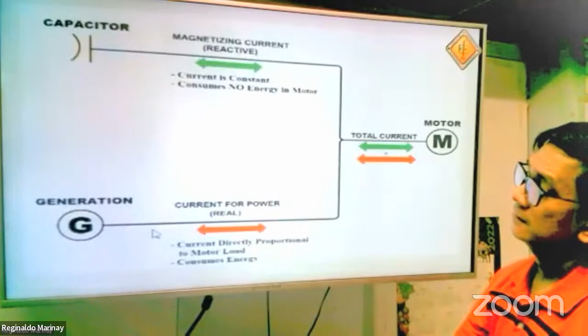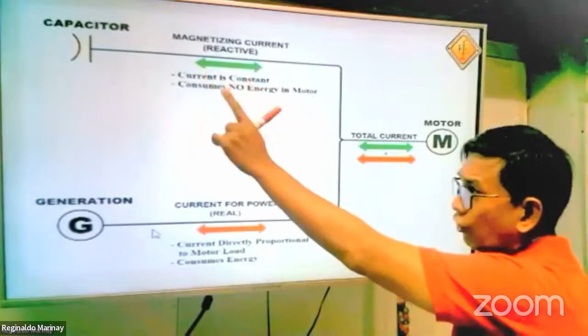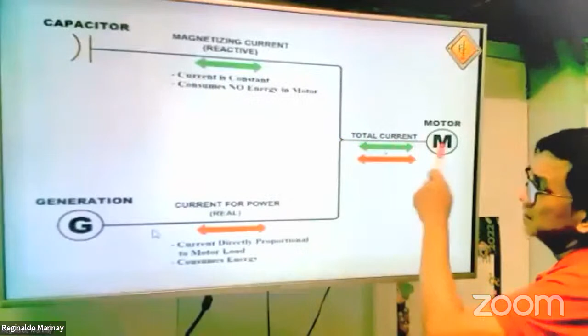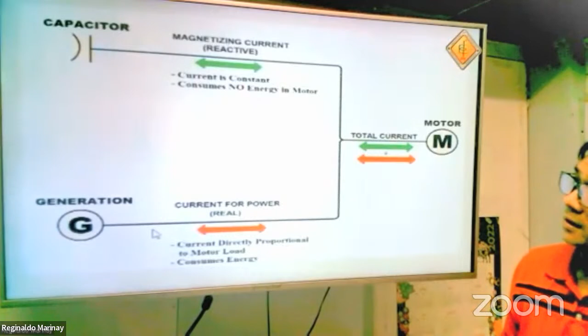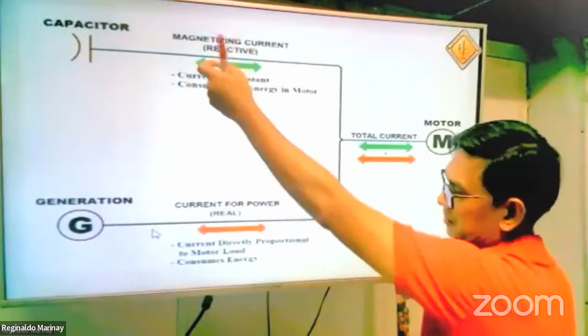Initially, it took these two types of current: the magnetizing current and the real current. But when you put a capacitor on the system, take a look—of course this is an ideal discussion for power factor correction, because you will see that the green color, the magnetizing or reactive current, is all being delivered by the capacitor. That is what I mean by ideal. But in reality, the source still delivers reactive current, but it decreases some reactive portion of the current here because of the capacitor current, which is the reactive current of the capacitor.